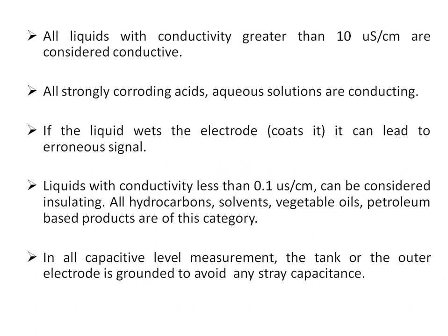All liquids with conductivity greater than 10 micro-siemens per centimeter are considered conductive; the unit of conductivity is siemens, also known as mho. Strongly corrosive acids and aqueous solutions are conducting. If the liquid wets the electrode it can lead to erroneous signals — a known problem with capacitance type sensors for conducting liquids. Liquids with conductivity less than 0.1 micro-siemens per centimeter are termed insulating; hydrocarbons, solvents, vegetable oils, and petroleum-based products fall in this category. In all capacitor level measurements, the tank or outer electrode is grounded to avoid stray capacitance and prevent errors.